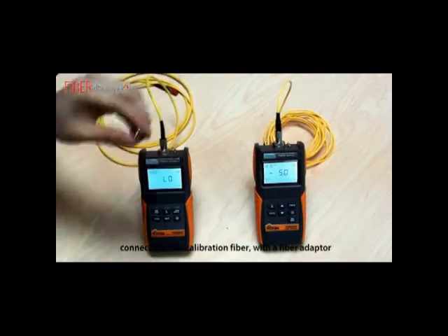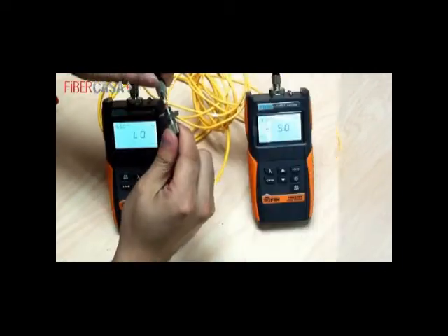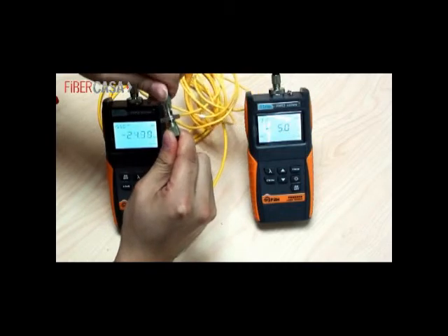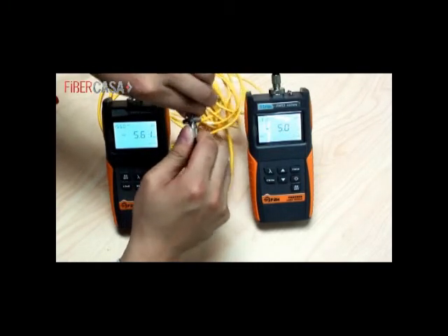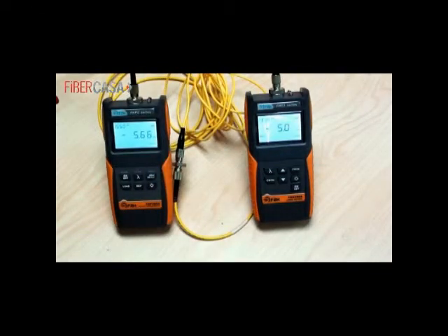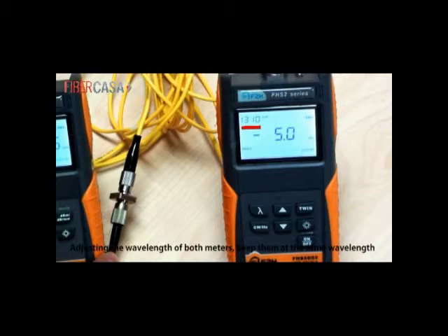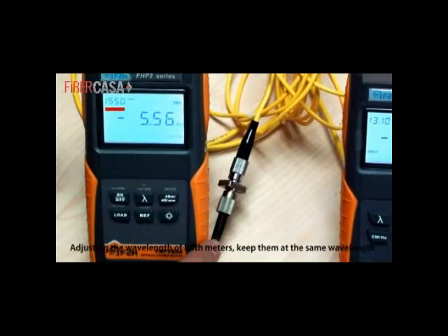Connect two calibration fibers with a fiber adapter. Adjusting the wavelength of both meters, keep them at the same wavelength.